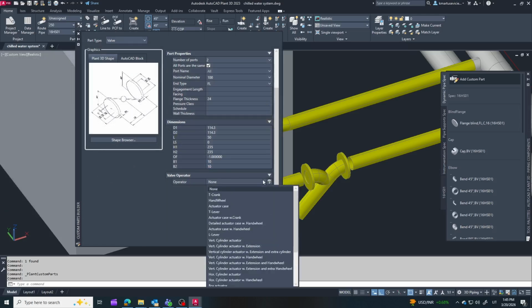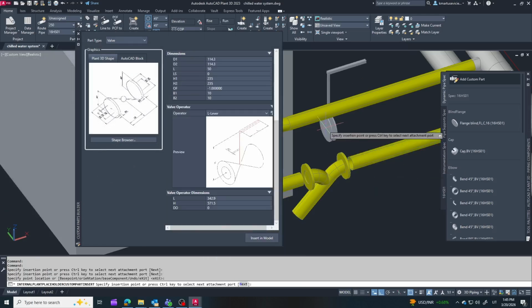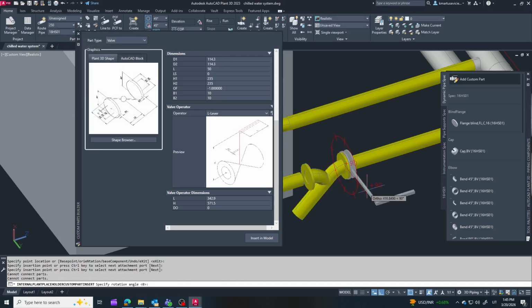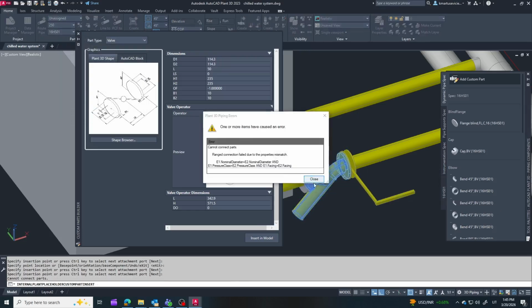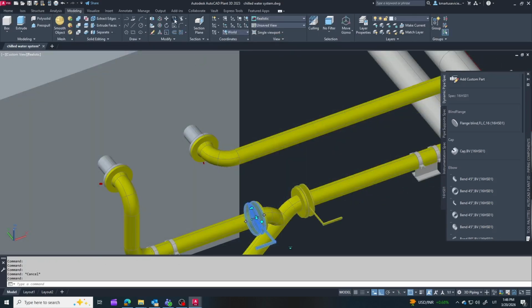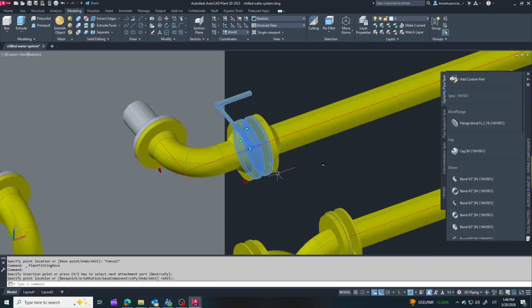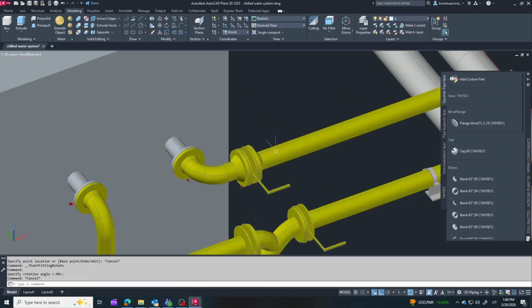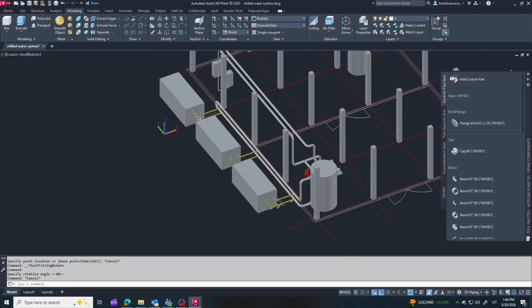In our case, I place the butterfly valves directly at the ends of a strainer. This creates a kind of sandwich arrangement. By using wafer-type butterfly valves, we can install them between flanges and reduce the number of separate connections. This helps save space and simplifies the installation. On the outlet line, we install an isolating valve and a balancing valve to control the flow.